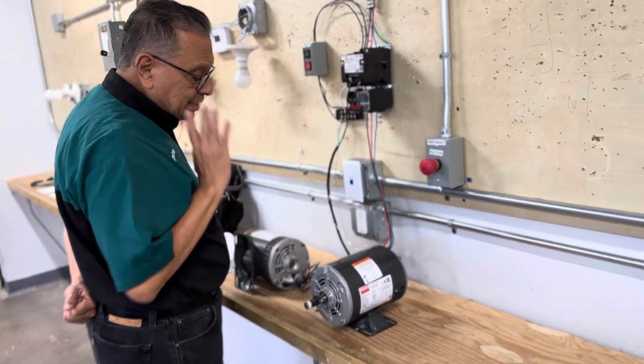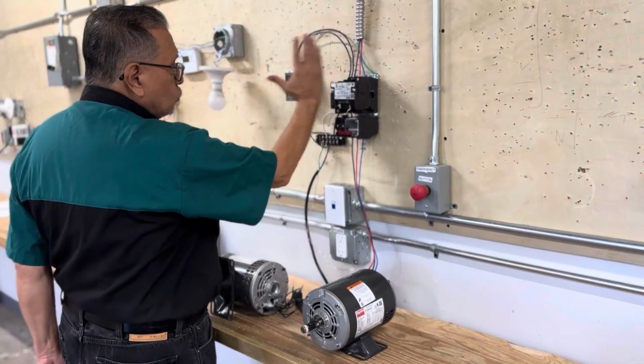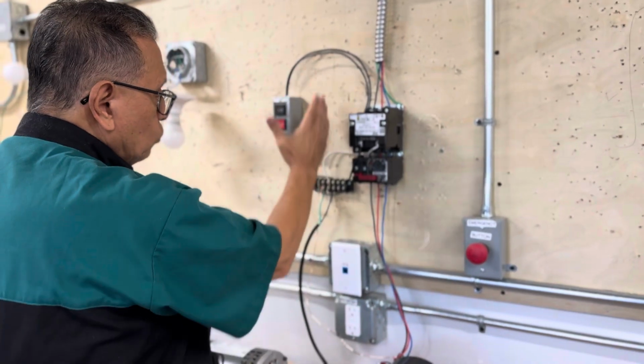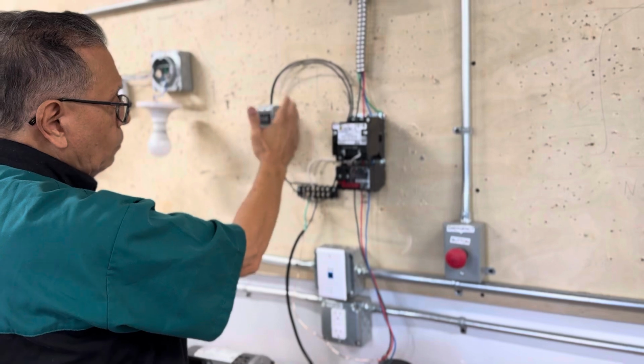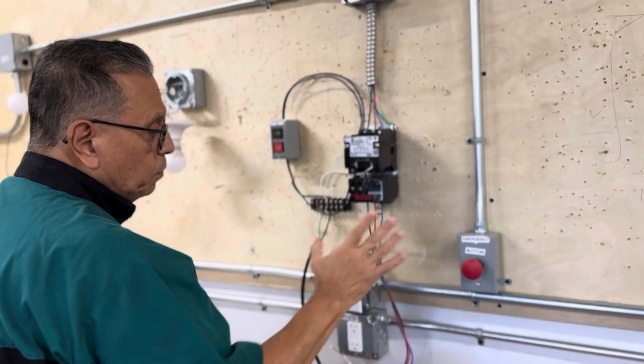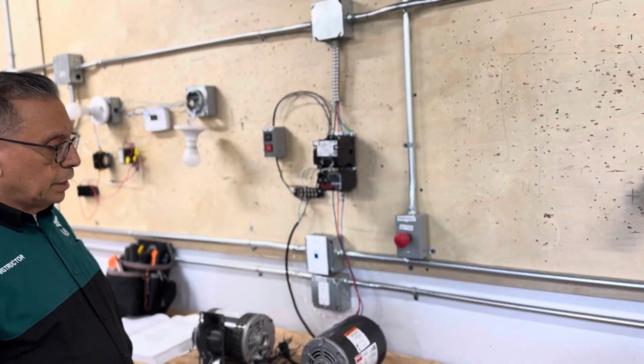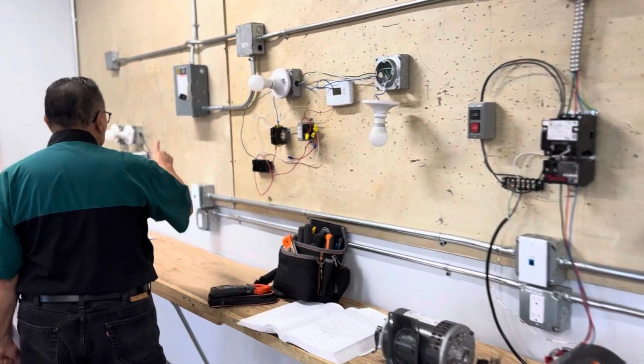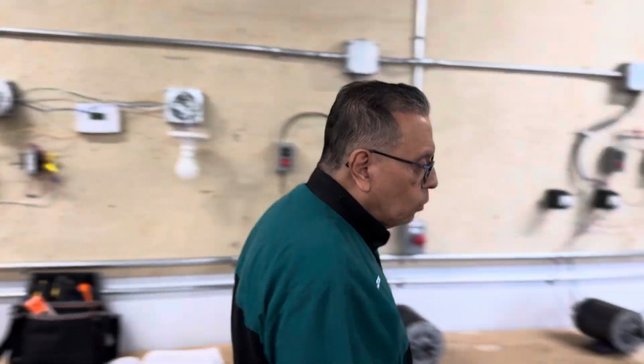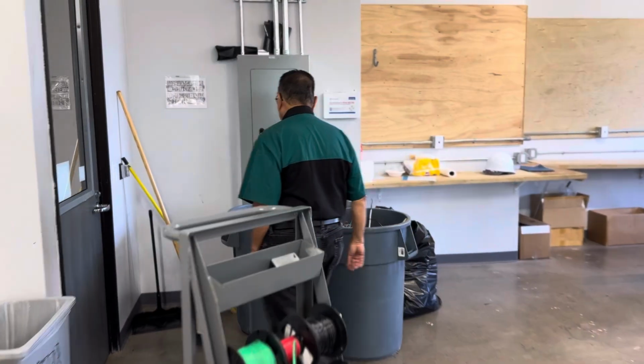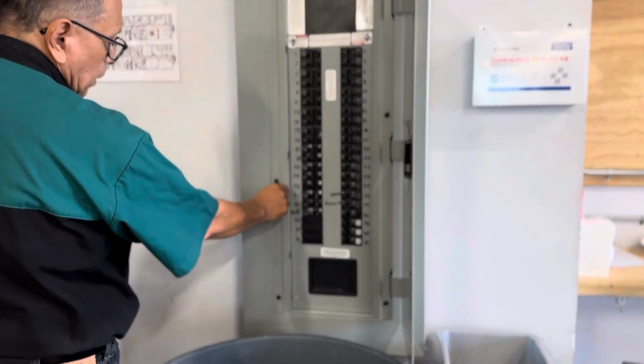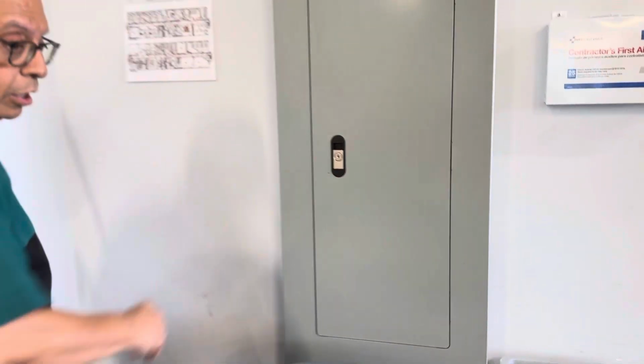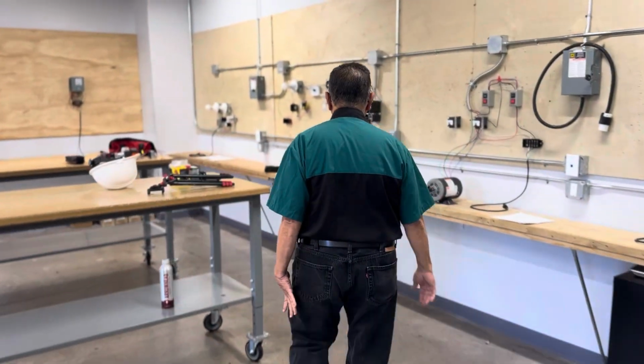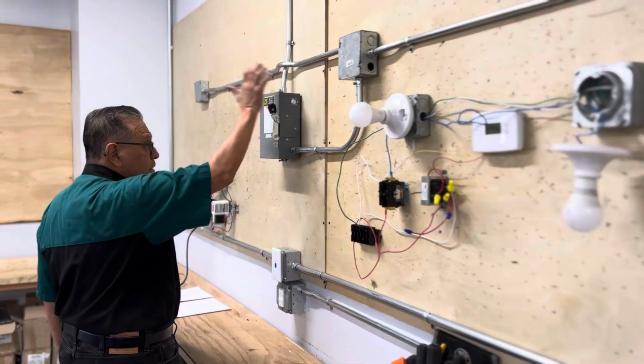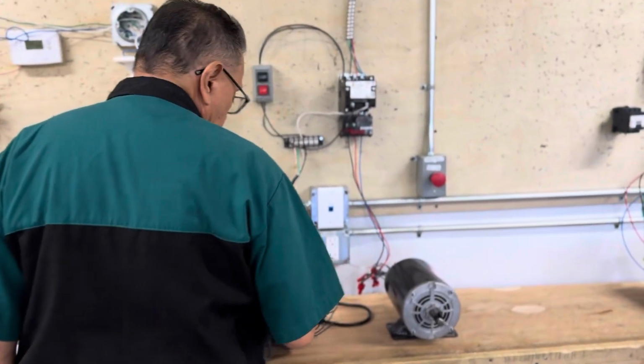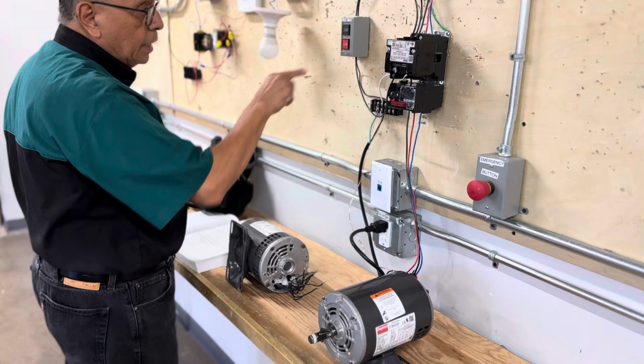Before I test it, I forgot to mention we have two sections here: the control part and the power part. The control part is normally also known as the low voltage section, and this is the high voltage, but keep in mind, high voltage for us is no higher than 600 volts. Now let me close the circuit breaker on the panel, because we have double protection: a circuit breaker and a fuse. Right here, 25, 27, 28 is closed. So I will test it now. I will connect the power part and start.